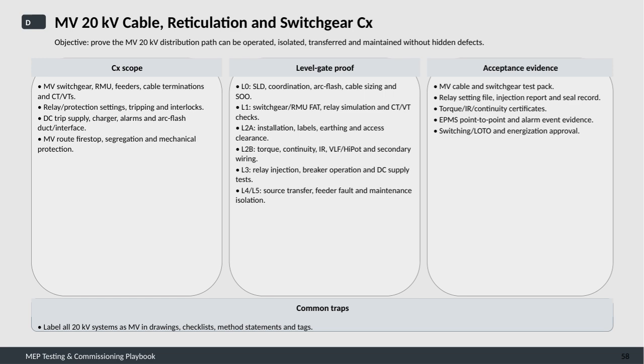Moving to the level gate proof, this is a step-by-step checklist that guides the commissioning process. Level 0 ensures key designs like single-line diagrams, coordination studies, arc flash analysis, cable sizing, and switching operation orders are all in place. Level 1 includes factory acceptance testing of switchgear and RMUs, relay simulations, and checks on current and voltage transformers. Level 2A verifies installation quality, labeling, earthing, and clearance access.